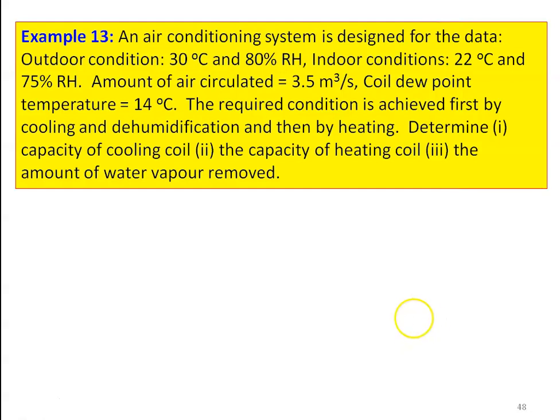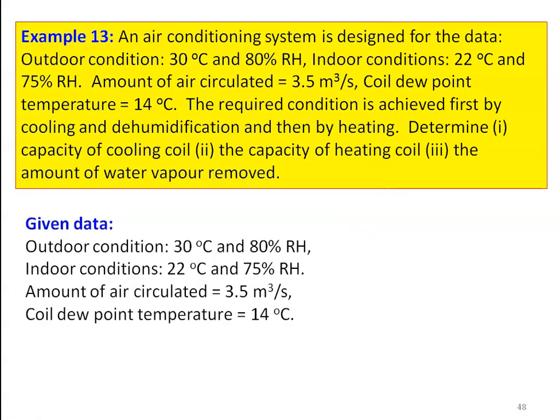Example number 13: An air conditioning system is designed with the following data. Outdoor conditions are 30°C and 80% relative humidity. Indoor conditions required are 22°C and 75% relative humidity. Amount of air circulated is 3.5 m³/s. Coil dew point temperature is 14°C. The required condition is achieved first by cooling and dehumidification, then by heating. Determine: capacity of the cooling coil, capacity of the heating coil, and the amount of water vapor removed.